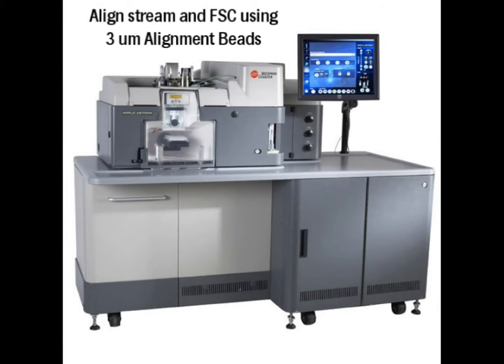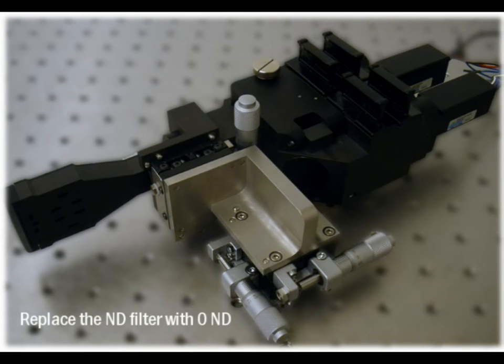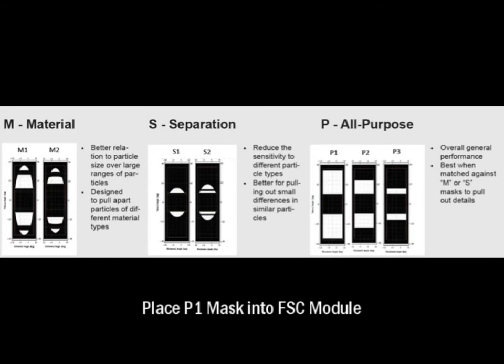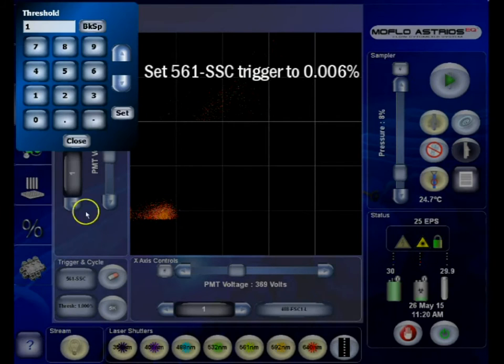Setting up the MoFlo Astrios EQ for less than 1 micron particle detection. First, align the stream and the forward scatter with the 3 micron alignment beads. Replace the ND filter with a 0 ND filter. Change the mask to P1.